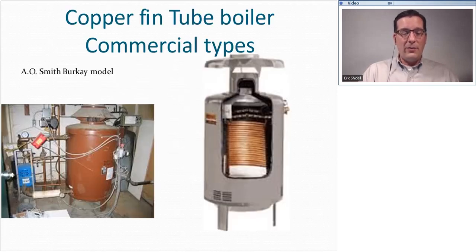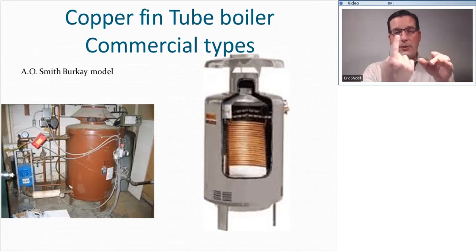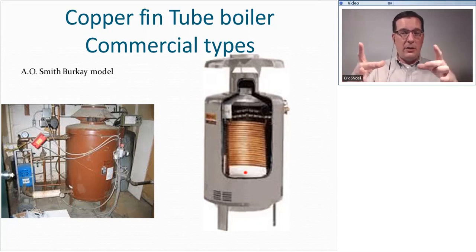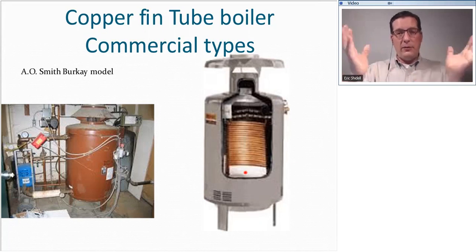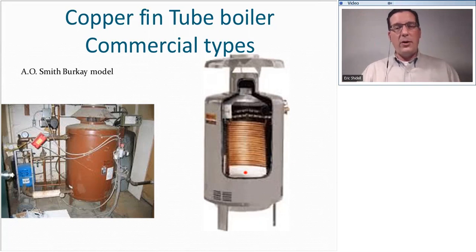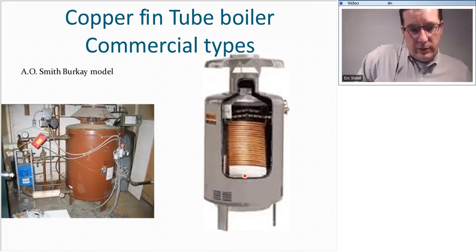We have another commercial style of copper fin boiler, called the A.O. Smith Burkay. It is unusual in that instead of copper tubes laying in a horizontal plane, they're wrapped around in a coil, with one giant burner in the middle, almost like a big water heater style burner. I call it the Olympic torch burner, that big round thing with the flames that come up like this. On these, they're probably in the 400 to 500,000 BTU neighborhood.